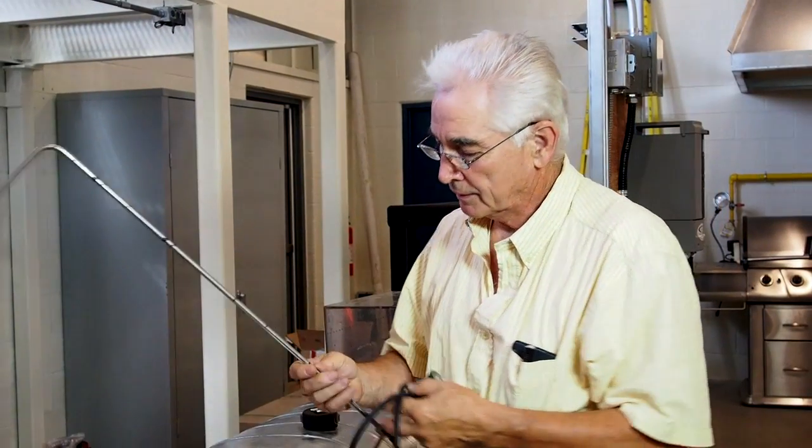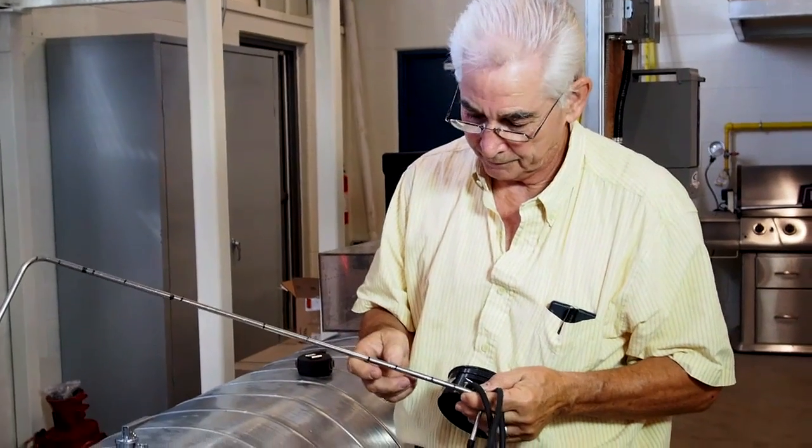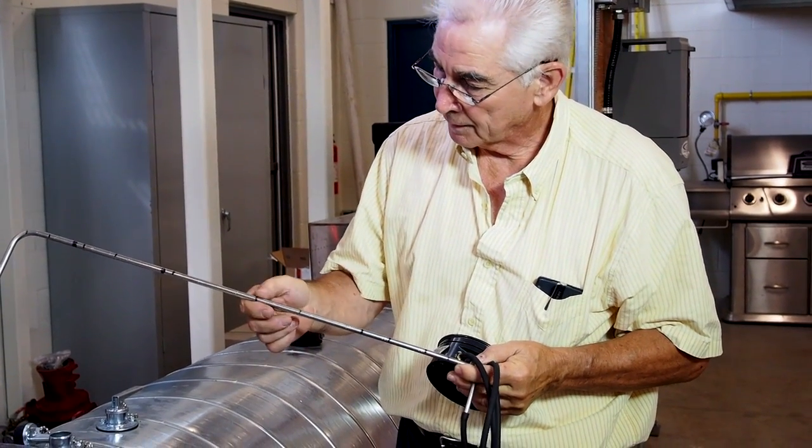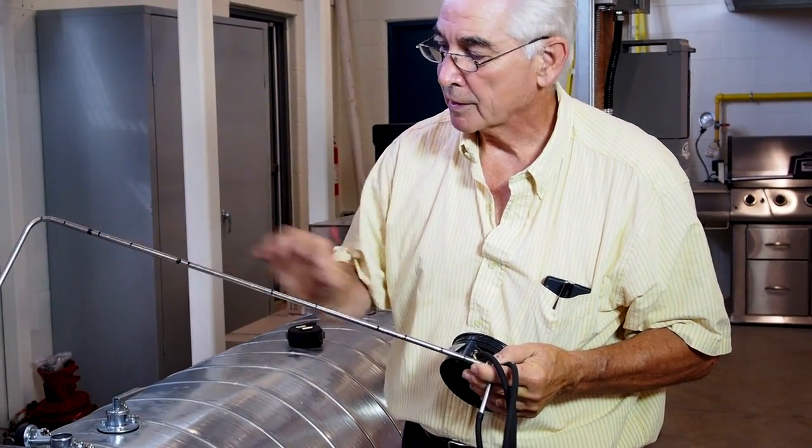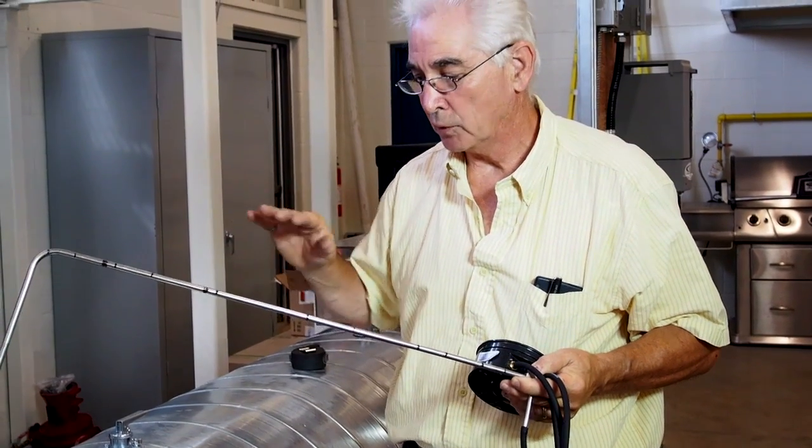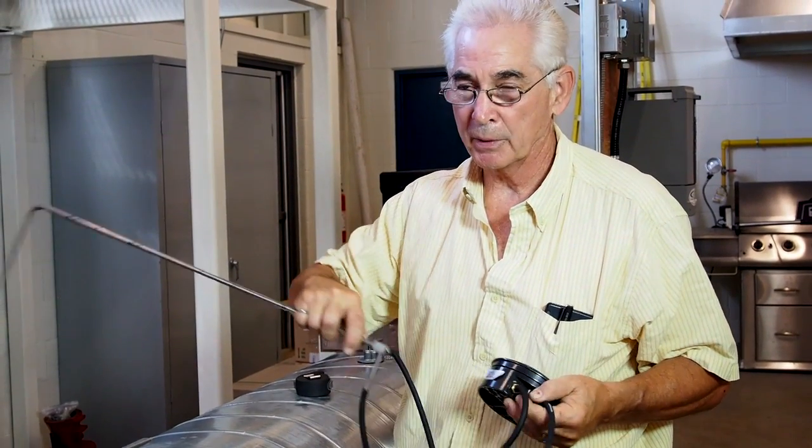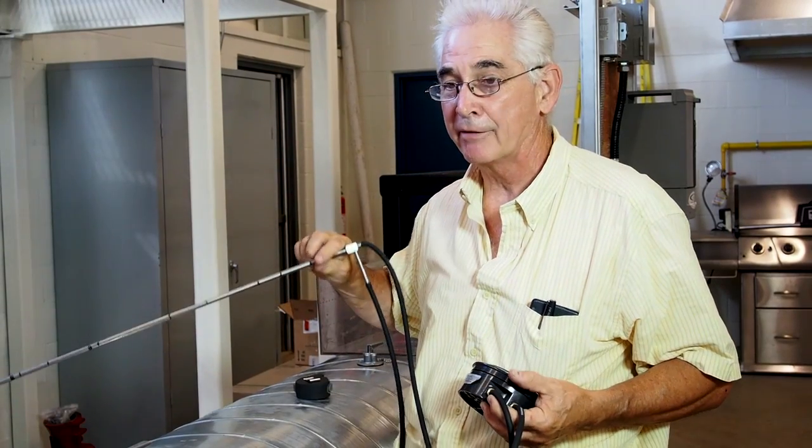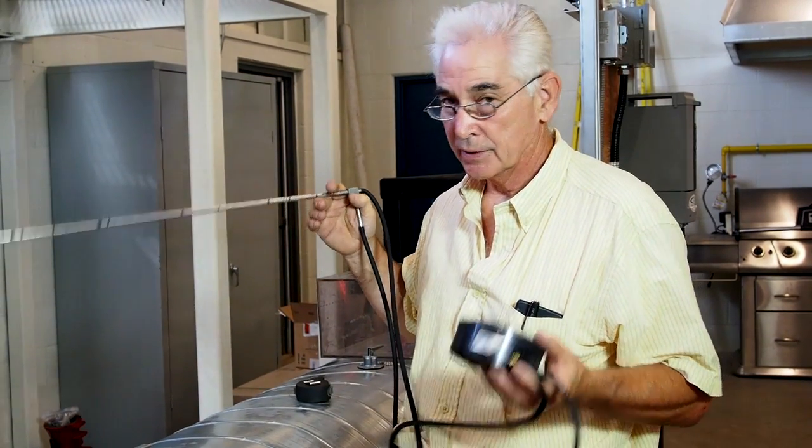For a round duct, the spacing isn't equal because we want to be at the center of equal annular areas. Remember, we're always trying to determine what's the average velocity in the duct. So, it's the same principle.